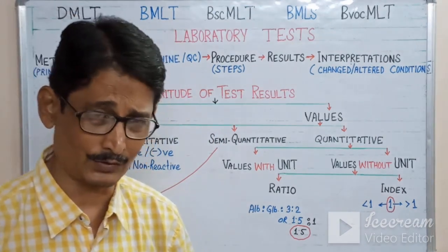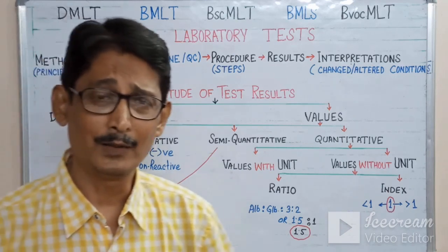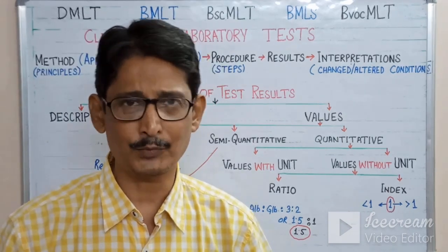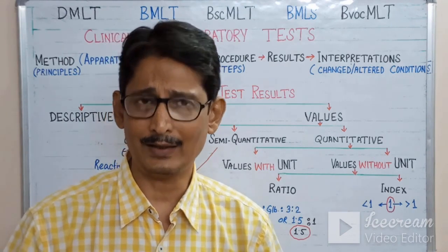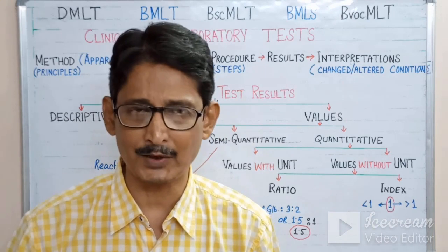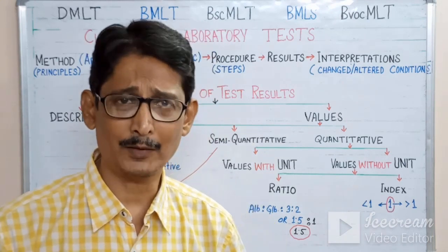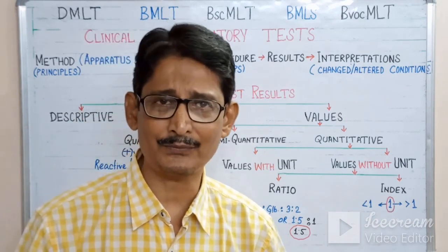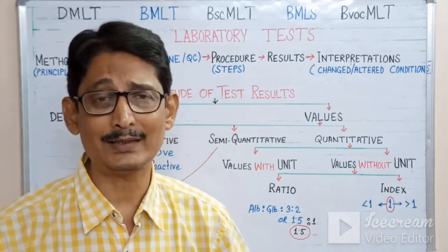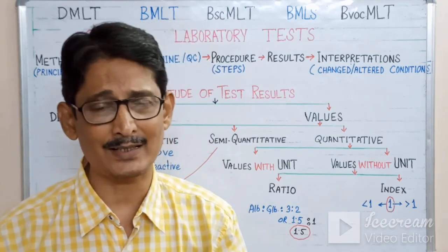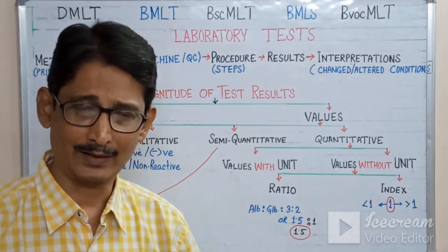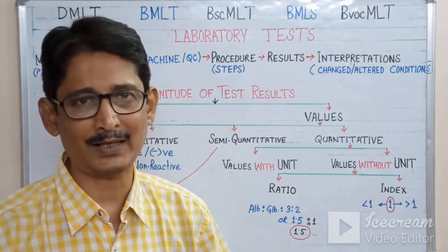This is quality control. Like in our laboratory, before we run a test, say today in the morning when my friends are collecting blood from the patients, myself or my other colleagues are running the quality control of the machine, to check that for the tests we are going to perform today, the machine is giving results as per the norms.